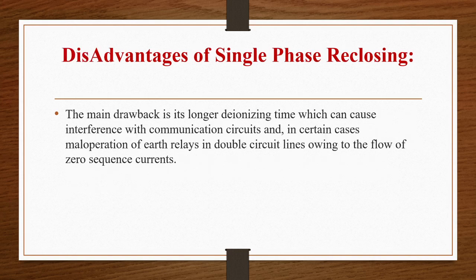So what are the disadvantages of single phase reclosing? The main drawback is its longer deionizing time, which can cause interference with communication circuits and, in certain cases, maloperation of earth relays in double circuit lines owing to the flow of zero sequence currents.